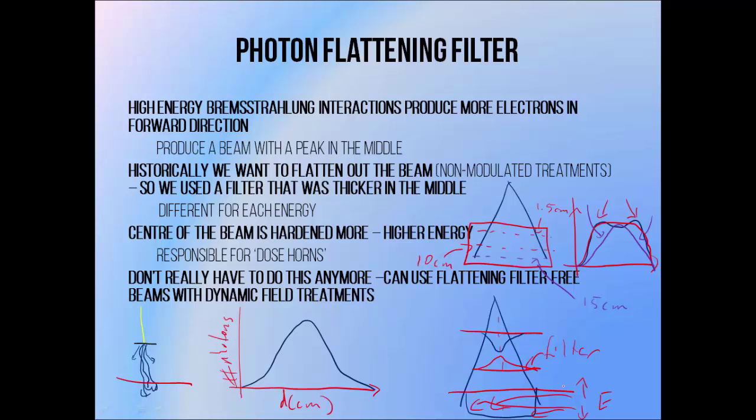These flattening filters absorb a significant portion of the beam, so they reduce the dose rate considerably. If you take the flattening filter out of the beam, you can get a dose rate about four times higher. A lot of the beam also scatters as it passes through the flattening filter, which can result in dose outside of the field, which isn't great for the patient. Flattening filters were historically quite necessary to obtain uniform, clinically useful beams, but with the introduction of intensity modulated treatments they're no longer quite so necessary, though they remain the default option for most medical linear accelerators.